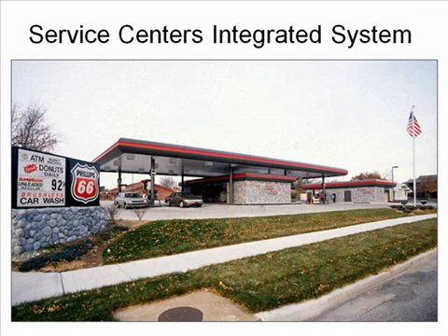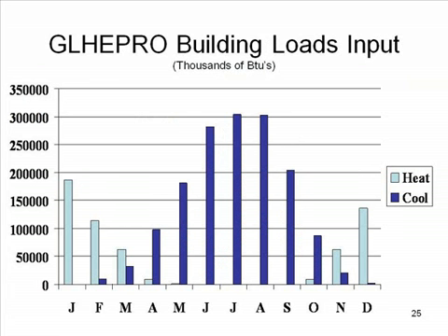In the design, if we've got more heat than we need, we have to make sure the piping lengths and separation distances are appropriate so we don't get a long-term temperature buildup — which some people have heard happened 30 years ago or last year. If that does happen, it was just a bad case of design. From that building, we're looking for a monthly load that's going to go to the ground heat exchanger.